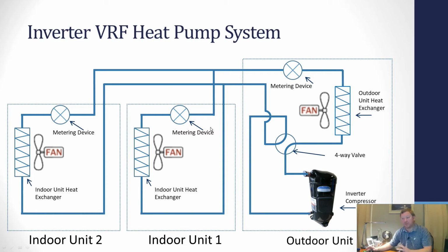So I know that's only two differences between the expansion valve and the control logic. It's just scratching the surface. There are so many other things that we can do, like with auto mode. It's a conversation for another day, but the basics is you don't want auto mode on a mini split, and there's a whole list of reasons why. On a VRF system, it's not that big of a deal. You can put it in auto because you're going to be controlling your zones to a much tighter deadband.